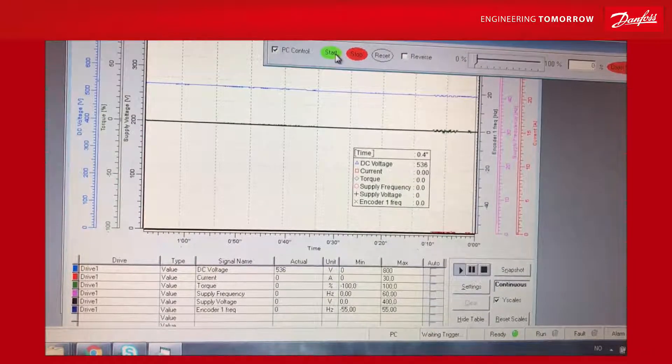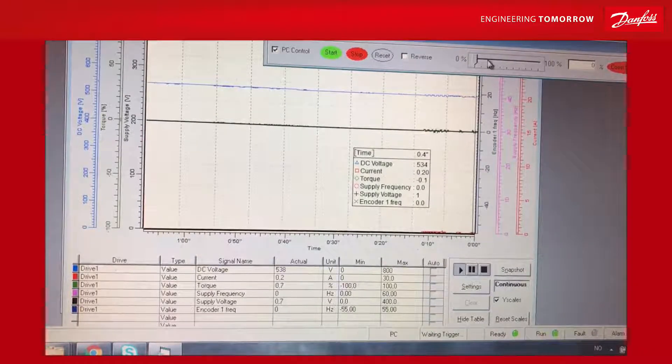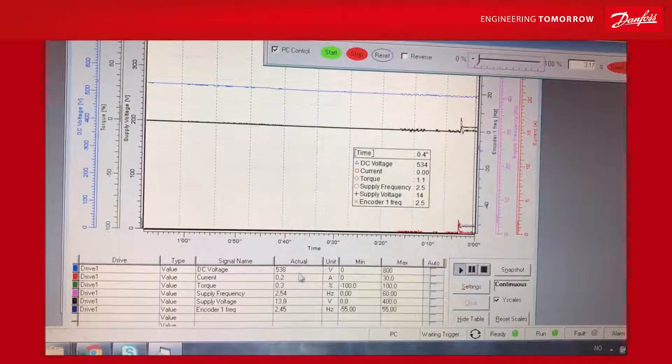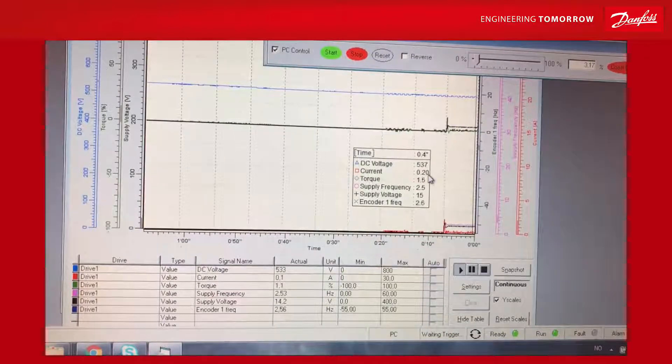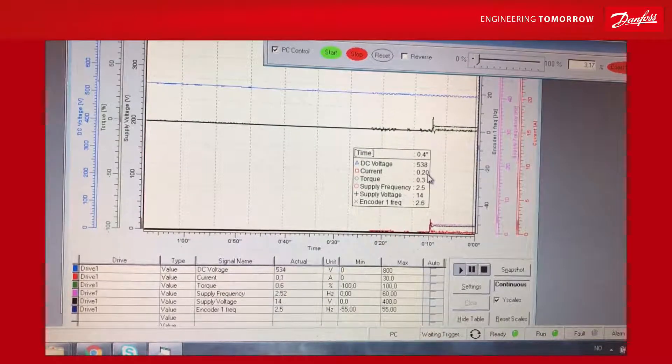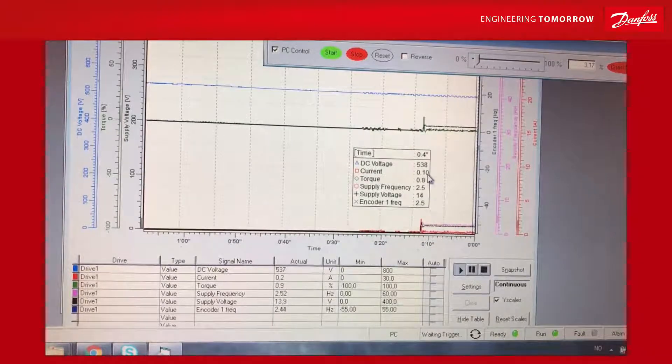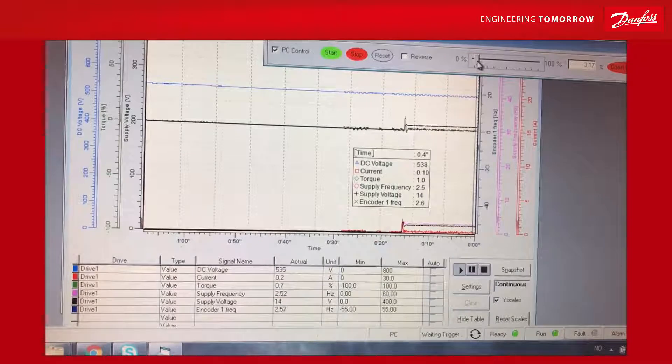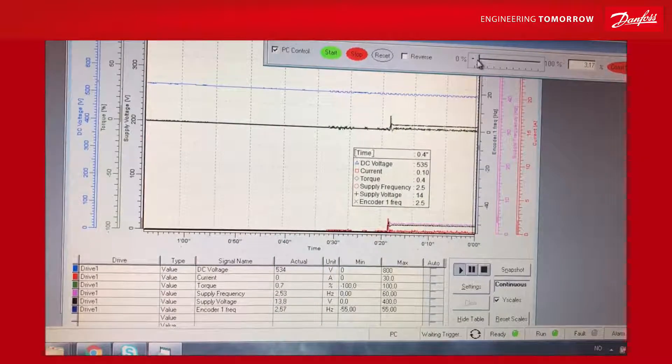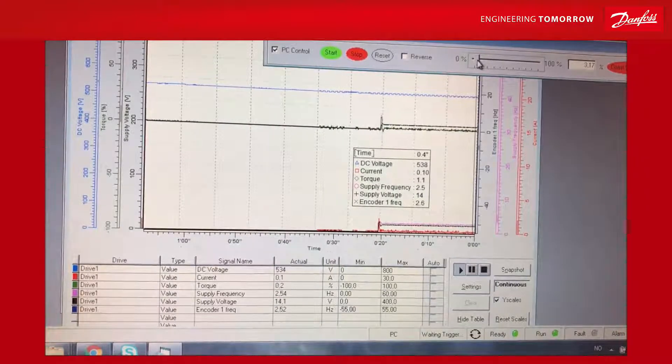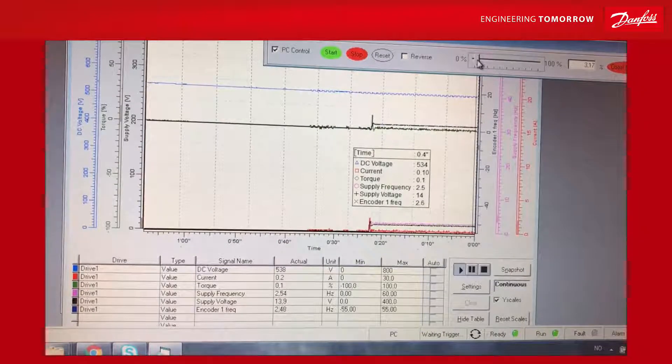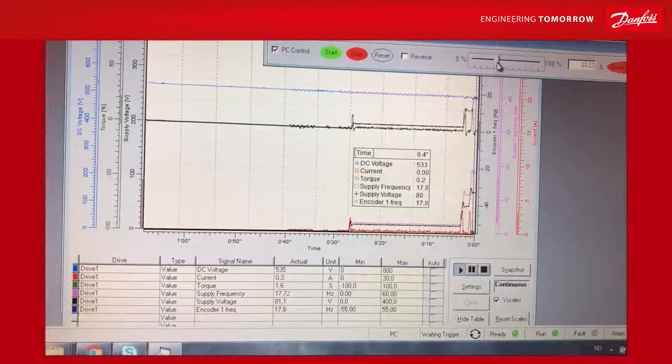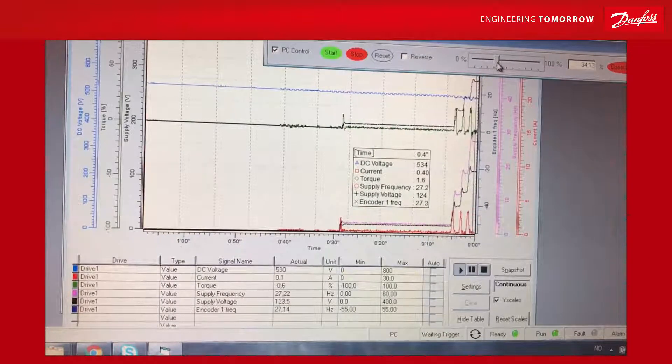There is no movement in the motor when we start it. We see that the current is very low, only 0.2 amperes. That is almost nothing compared to when we run it in open loop. In closed loop, it doesn't use more current than needed. There's no reactive current going on before you actually need it. It runs smoothly and nicely.